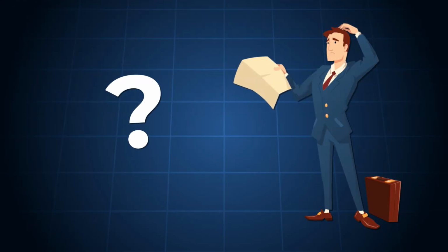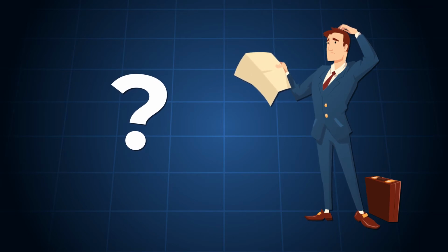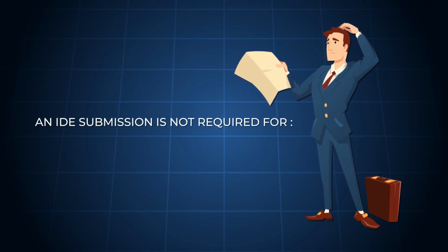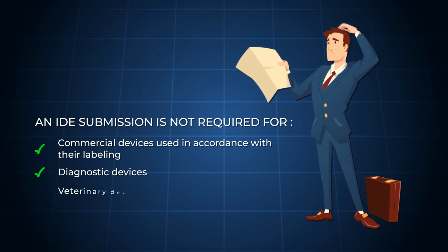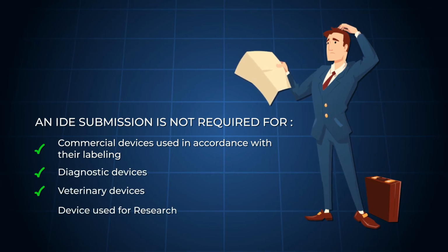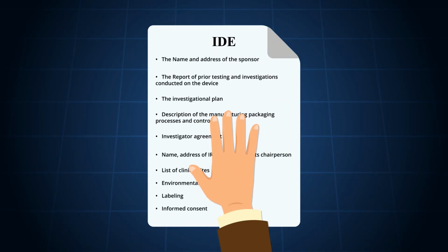When don't you need to submit an IDE to FDA? This is called IDE exempted. An IDE submission is not required for commercial devices used in accordance with their labeling, diagnostic devices, veterinary devices, and devices used for research. What is the content of a full IDE submission?